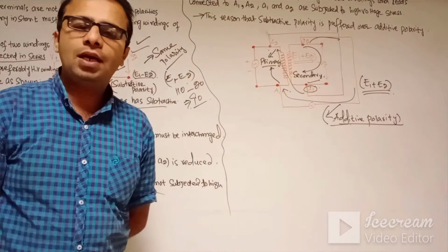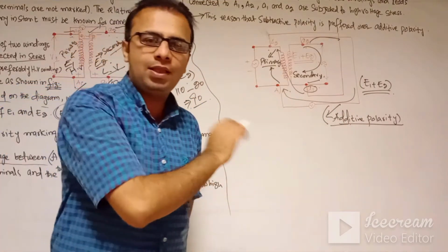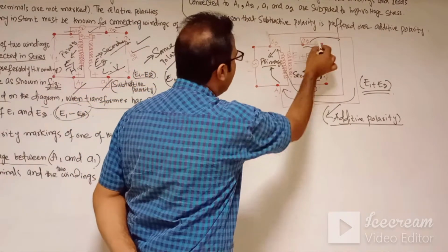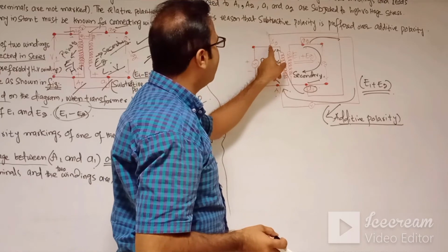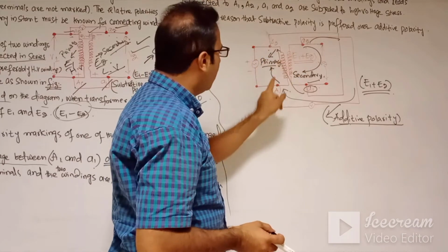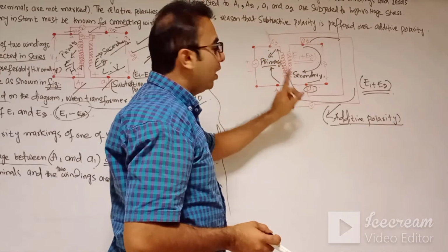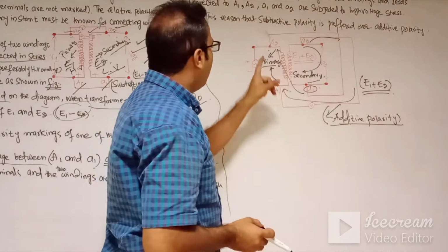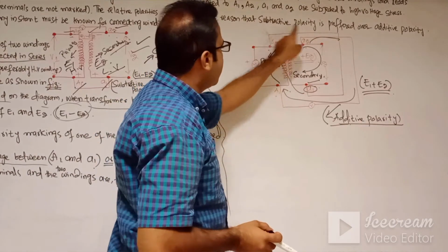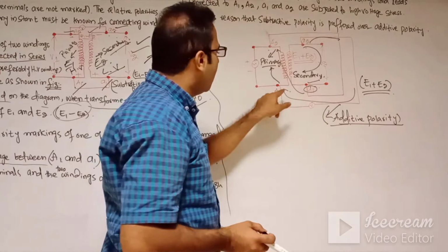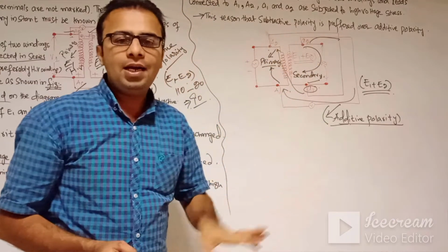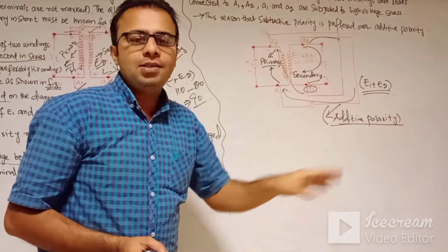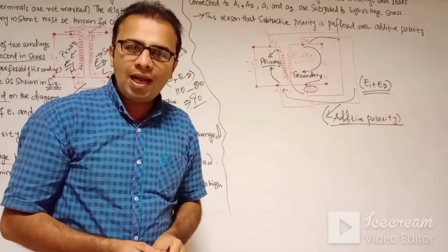Across these, we can easily connect the voltmeter in parallel with the two windings. You can see that previously we connected in series, like A2 with A2 and A1 with A1. Here in the opposite polarity, A2 is connected with A1 of the secondary side, and A1 of the primary side is connected with A2 of the secondary side, and between those leads we connect the voltmeter in parallel.